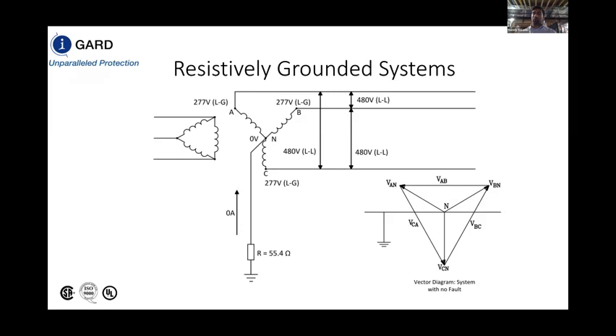In this particular schematic, we have a 480 volt line-to-line voltage system. And as you can see, we've placed a resistor from the neutral point to ground with a resistance of 55.4 ohms. Effectively, this resistor will limit any future fault occurring in the system from phase to ground to 5 amps. Our line to line and line to neutral voltages are still intact at the moment because there's no fault in the system at 480 volts and 277 volts respectively. Now let's see what happens when a fault occurs in the system. So the fault occurs on phase C.